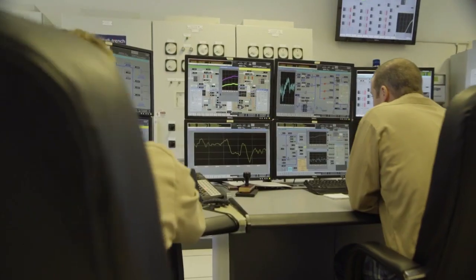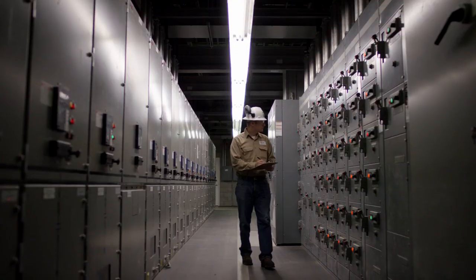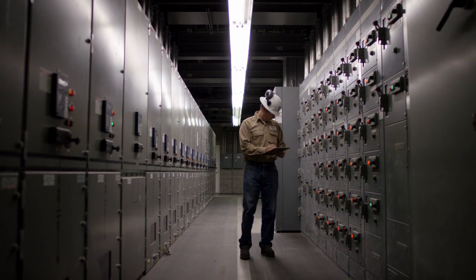So it's a geothermal facility that's air-cooled. You come out of the nighttime when it's cool with high power generation, and then that dips down during the course of the day as it warms up. So in the heat of the summer, the power we were getting was at minimum, from a geothermal plant.